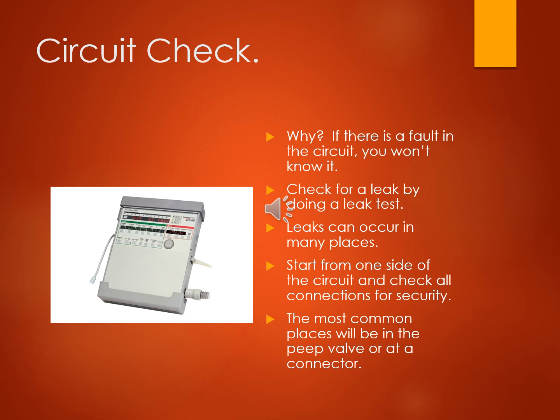There's been too many times I've gone to see if I can help a transport team assess their ventilator because they're not understanding what's going on, and I always think it's the patient that's causing the problem. But if there's a leak in the system when you are turning it on, you will always continue to think it's the patient that has the problem and not necessarily the ventilator. So do yourself a favor, check the equipment, check for a leak by doing the leak check.